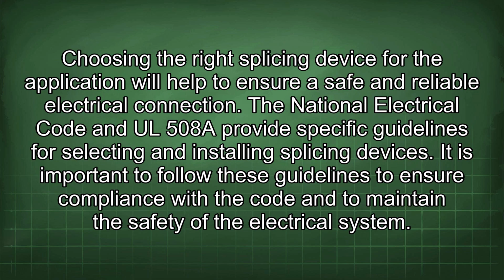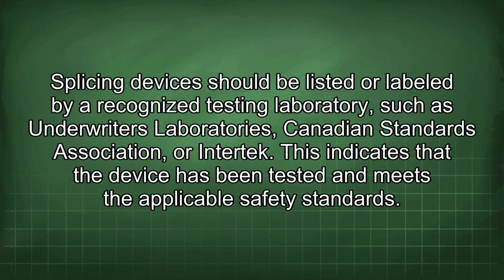The National Electrical Code and UL 508A provide specific guidelines for selecting and installing splicing devices. It is important to follow these guidelines to ensure compliance with the code and to maintain the safety of the electrical system. Splicing devices should be listed or labeled by a recognized testing laboratory, such as Underwriters Laboratories, Canadian Standards Association, or Intertek. This indicates that the device has been tested and meets the applicable safety standards.